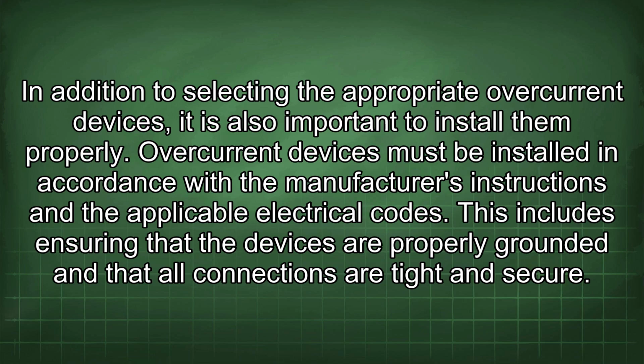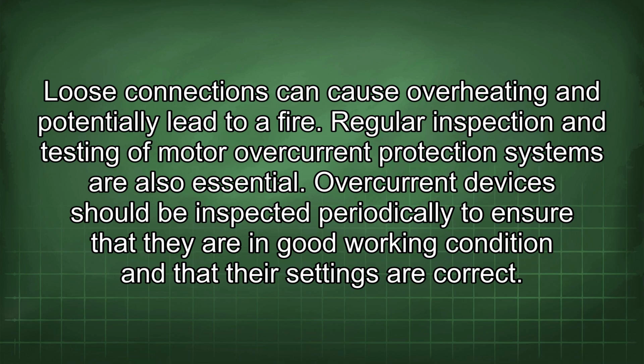In addition to selecting the appropriate overcurrent devices, it is also important to install them properly. Overcurrent devices must be installed in accordance with the manufacturer's instructions and the applicable electrical codes. This includes ensuring that the devices are properly grounded and that all connections are tight and secure. Loose connections can cause overheating and potentially lead to a fire.